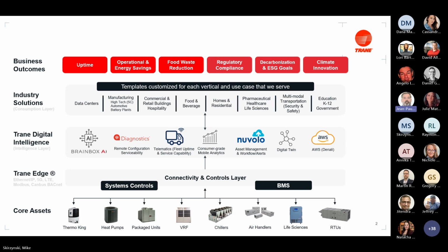So if the system is saying it wants a supply temperature of 18 and your analytics say it should be 15, you override the programming. You basically take remote control of the building systems off the existing BAS. Yeah, we pull set point levers and schedule levers, those are the two most common levers. And at any point you can release it, it's right there in the priority array being overridden. You'll see BBAI controlling the discharge air set point of air handler 17. If you don't like it, just remove it or override it.